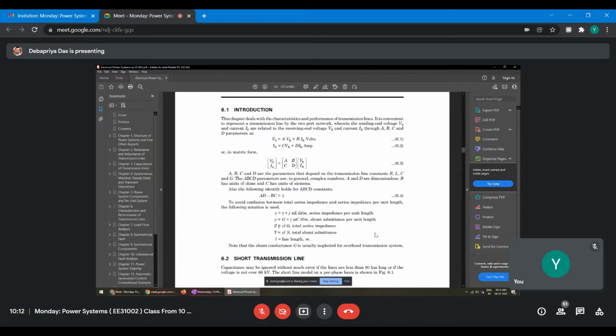Capital Z equals small z into L, where L is the length of the line. So total impedance will be small z into L, giving Z in ohms. Similarly, shunt admittance Y equals small y into L, in Siemens or mho, where L is the line length in meters. So these are the nomenclature. This is R, not gamma - that was a typographical error.